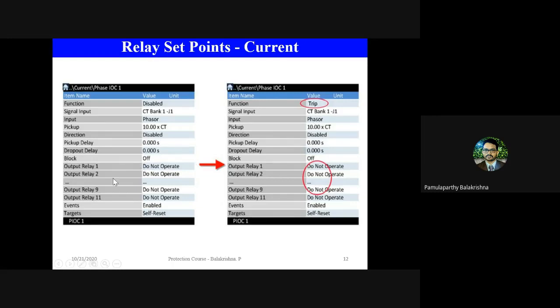It is disabled. Then you have various output relays like 1 to 11. What this 1 to 11 means is that in the relay hardware there are 11 digital output relays. You can select any one or any two. It is up to you which digital output relay inside the relay hardware will send a signal to the breaker if this particular overcurrent condition occurs. So that you will define here. Just by defining, it doesn't happen. When you select output relay 1, here it is mentioned do not operate, but when you select this as operate, then when you see an overcurrent function, the output relay 1 status will change, and this relay 1 should be connected to the circuit breaker input, and this will execute the trip, energize the trip coil, and then the trip coil energization will pull the breaker contacts. So you have to properly map this to the breaker side also. Basically it is defining which relay will give the signal to the breaker.